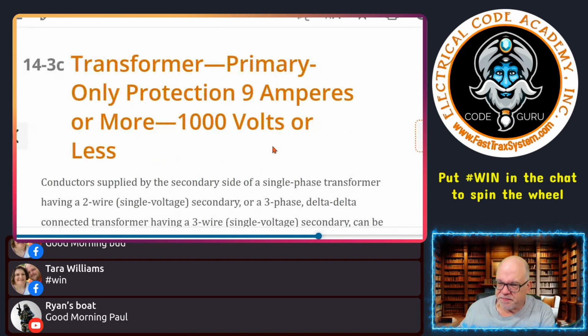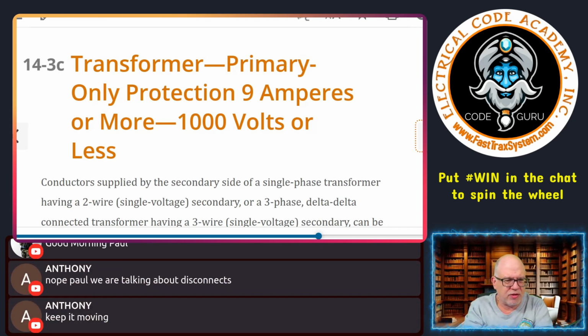Okay, so the number one transformer thing that we all talk about is protection for the transformer. We'll talk about the primary protection. I think in most cases, not all, because you could have some that are less than 9 amps. Very small application, very specific. Probably as an electrician, it's not what you're going to deal with every day. You're probably dealing with transformers every day that are 150 amp, 125s, 225s, that type of thing.